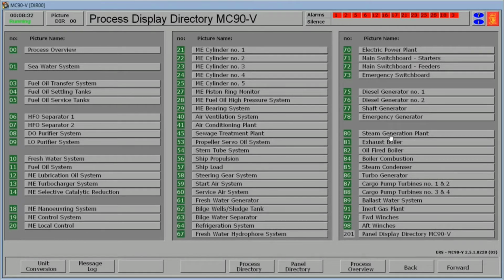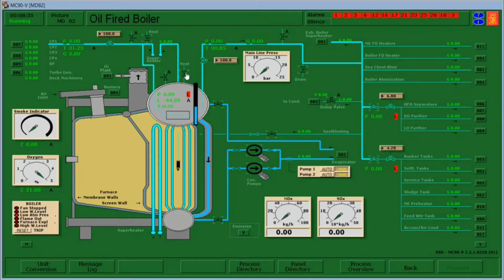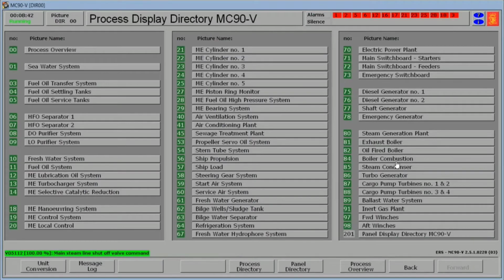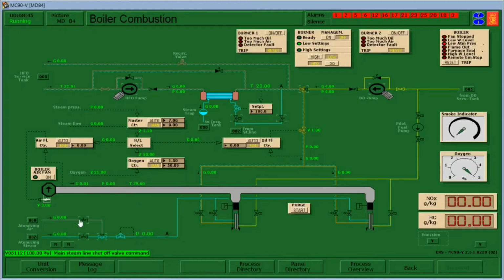the steam generation plant. Oil fired boiler. We open the vent, close the steam line. Then for the boiler combustion, open the atomizing air shutoff valve and click the 3-way valve. Open the boiler air fan. Set the airflow to 100. Set the master control to 10. Oxygen control to 10. Oil flow to 10.